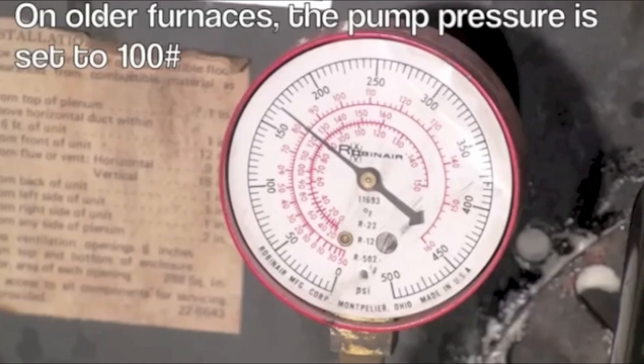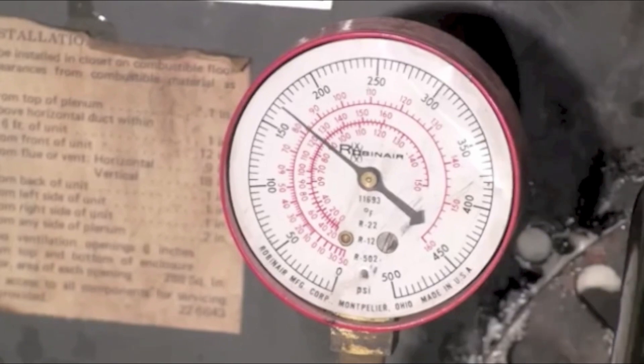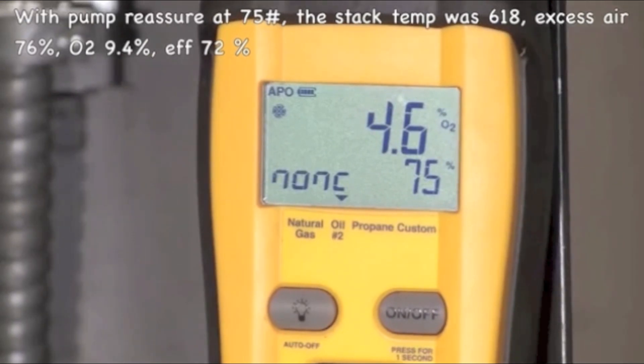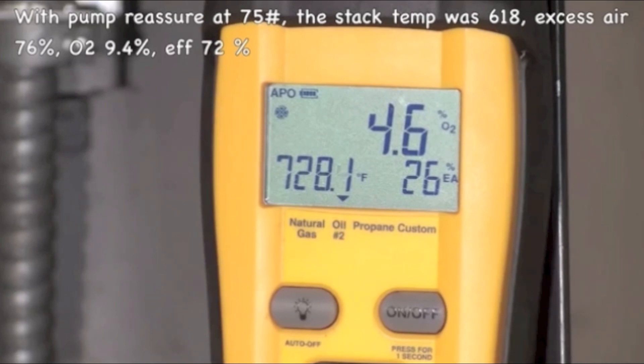The next thing we did was raise the pressure from 100 pounds up to 165 pounds and then did a combustion analysis at that pressure. We got a little bit of a surprise — efficiency was at 75% and O2 was 4.6%, all with a clean smoke. But what really threw us was the stack temperature: 728, compared to 618 at 75 pounds of pressure. Excess air was 26%, so that's not too bad.